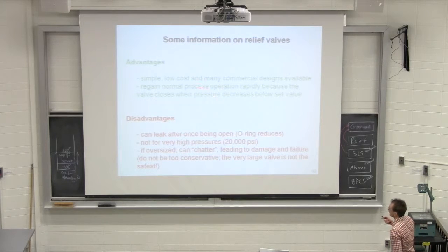And the valve closes back again. That's the important part. It recloses and you can keep operating your process. That's why I say sometimes you see relief valves are abused in this way, because a company will set that relief valve pressure and they will use it almost like a process control to regulate the pressure inside the tank. Right? And that's really not the right way of dealing with it.